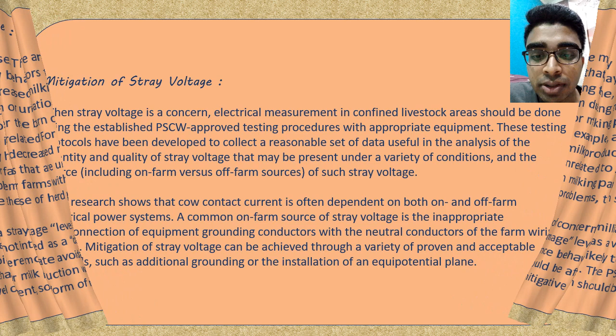Last is the mitigation of stray voltage. When stray voltage is a concern, electrical measurement in confined livestock areas should be done using established PSCW-approved testing procedures with appropriate equipment. These testing protocols have been developed to collect a reasonable set of data useful in analyzing the quantity and quality of stray voltage that may be present under a variety of conditions, and its source.